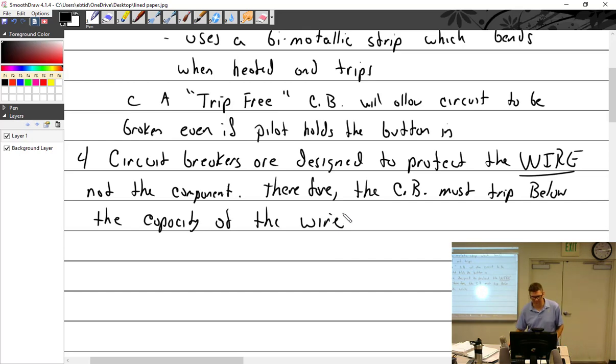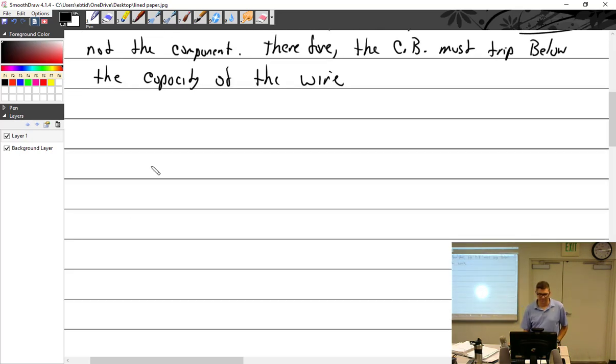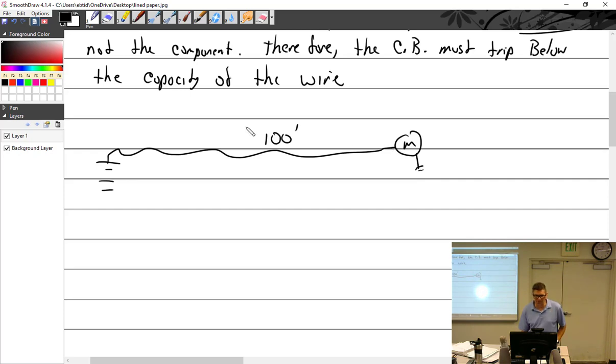So thinking about the flow: I've got a battery, and this wire runs 100 feet and finally gets to the motor. You're like, oh wait, I forgot to put a circuit breaker, so we'll put it right here, right at the motor, back in the tail. So you're saying don't do that, because the 100 feet of wire before it is still unprotected and that's going to burn.